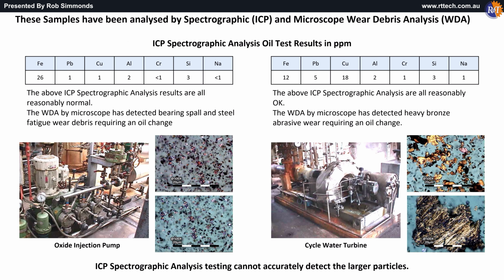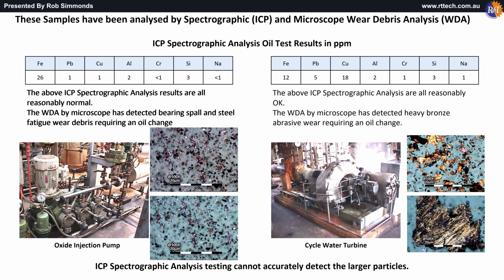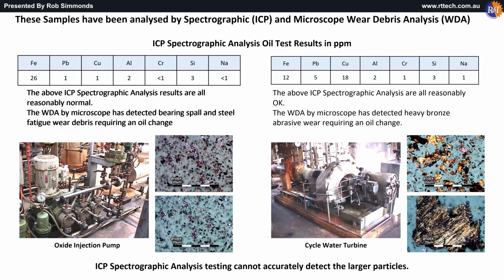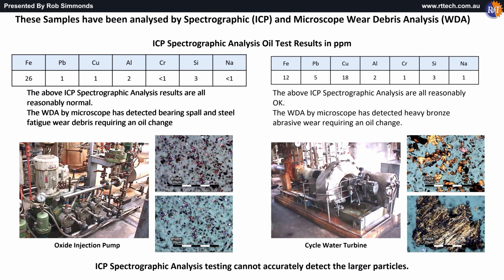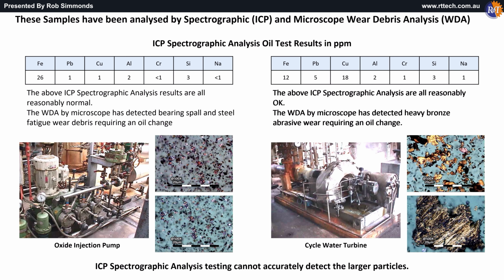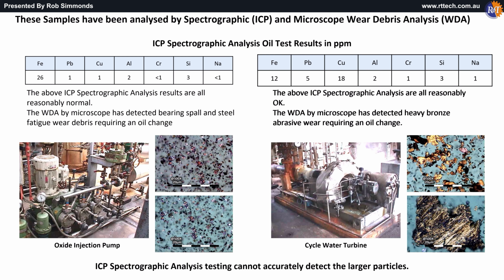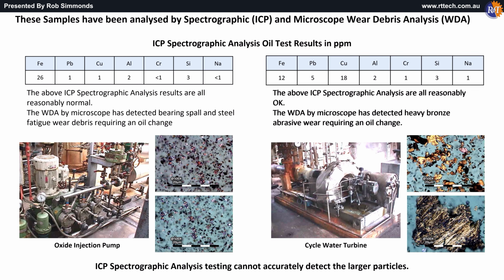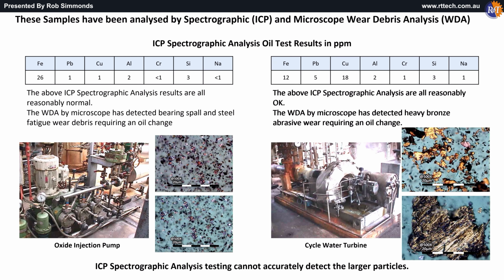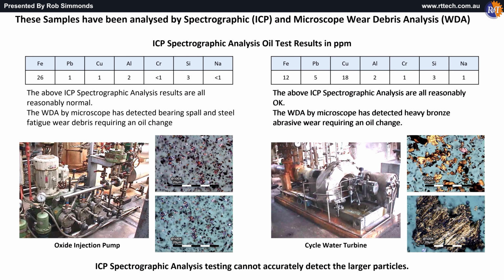These samples have been analysed by spectrographic and microscope wear debris analysis. On the left, we can see the above ICP spectrographic analysis results are reasonably normal, but when we check below with the microscope, we detected a bearing spall and steel fatigue, all requiring an oil change. Note how these particles were not detected in the above. On the right-hand side, the spectrographic analysis results are reasonably okay, and when we check the oil sample with the microscope, we can see there's heavy bronze wear that requires an oil change, displaying the difference in detection limits between the two.